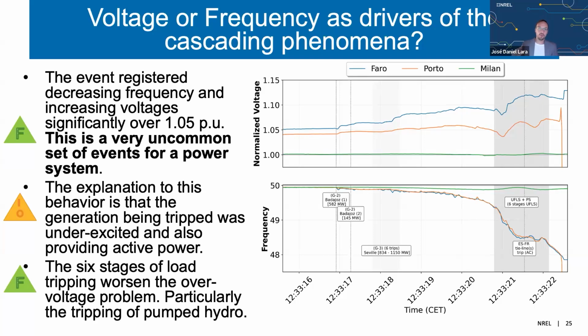And this is a very uncommon set of events for a power system engineer to see. Because as a power system engineer, you actually learn that when the system is overloaded, voltage and frequency drop together. And when you're trying to stop a blackout or a cascading event, those two things can happen at the same time, right? We talk about voltage collapse, we talk about system collapse. And this behavior is actually pretty uncommon. And I think that in the last IEEE general meeting, Professor Kostas Bournas was the one who said that this was observed once in an island in Greece, but it's very uncommon.